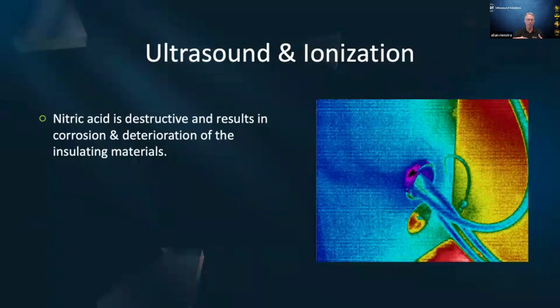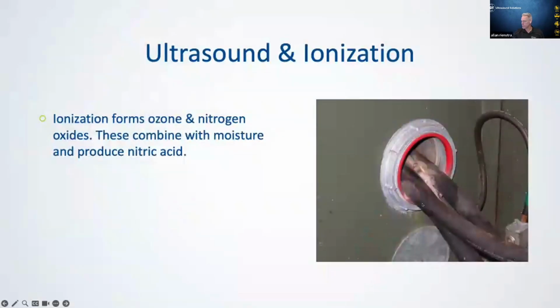If it's left unchecked long enough, you don't need ultrasound to find it. You just need common sense and good eyesight, because a lot of the times you'll start to see, I'll go back to this slide, you can see there's corona, this white powder around here. That's the ionization of ozone and nitrogen oxide forming, and it's pretty apparent. But ultrasound being able to detect things early in the P to F curve would have heard this long before it became visible for us.